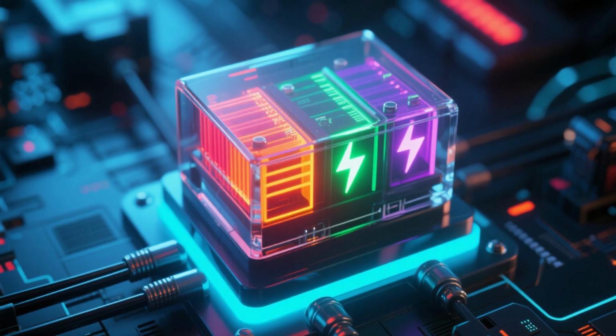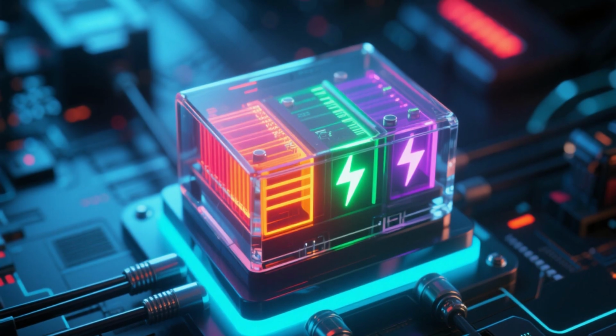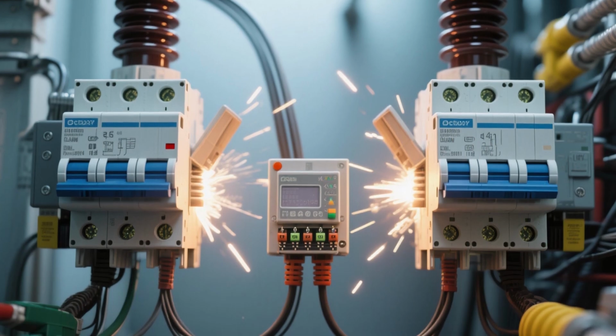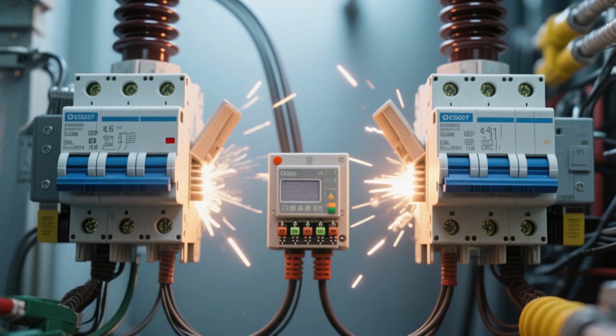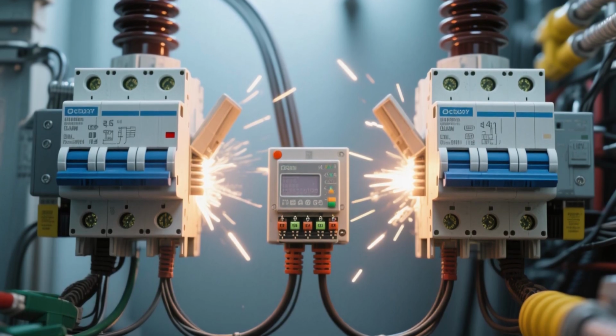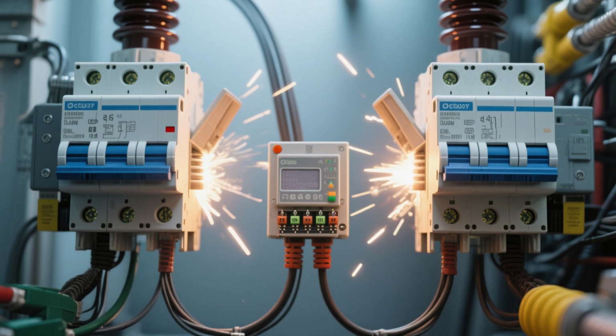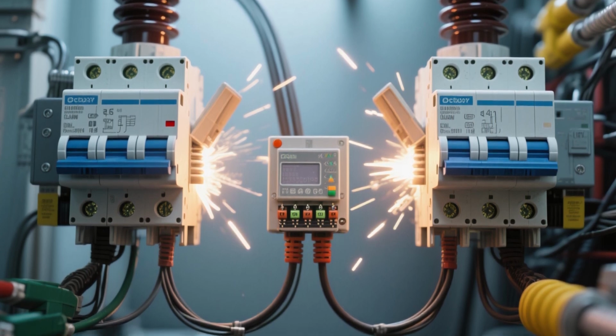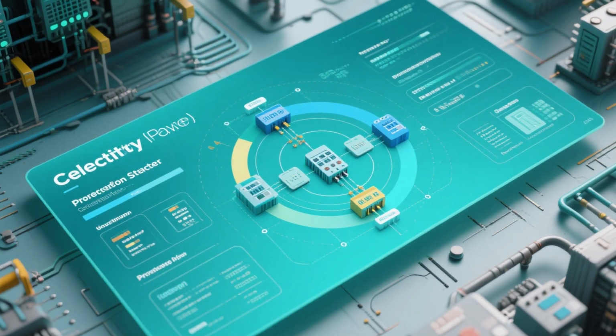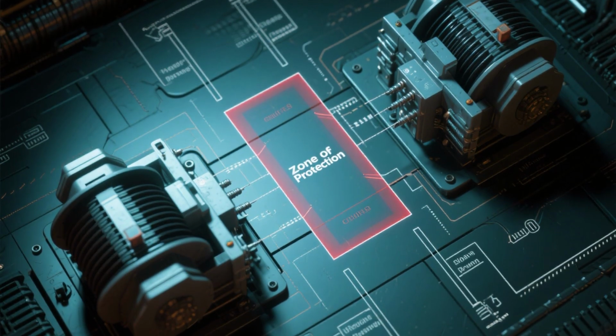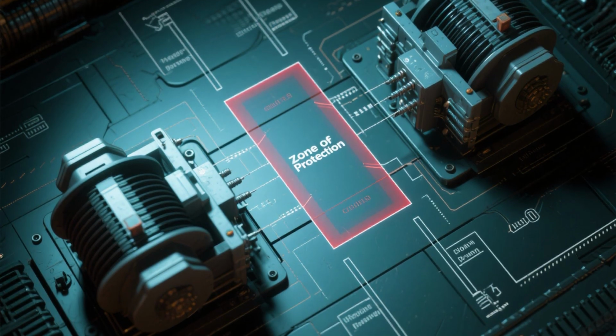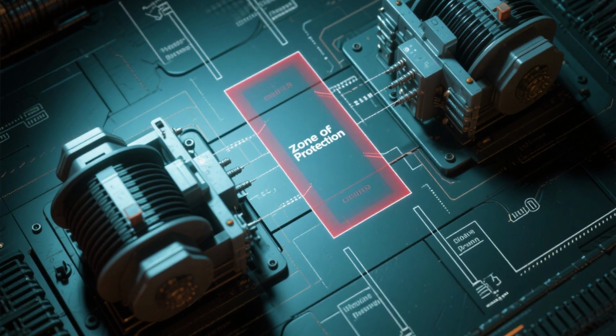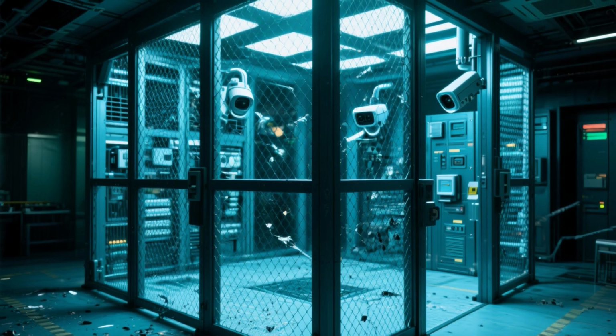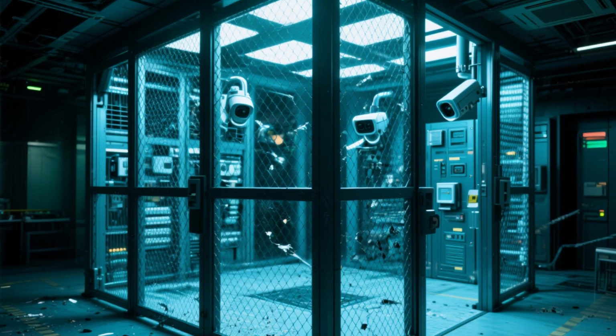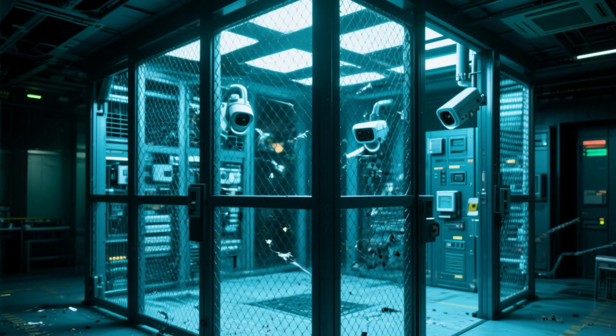The differential relay will detect this difference, or spill current. If this difference exceeds a set threshold, the relay concludes there is an internal fault and issues a command to open the circuit breakers at both ends, isolating the faulted line. The great advantage of differential protection is its selectivity. It only responds to faults within its defined zone of protection between the two current transformers. It is inherently immune to faults outside this zone, which prevents incorrect tripping during disturbances elsewhere in the grid.